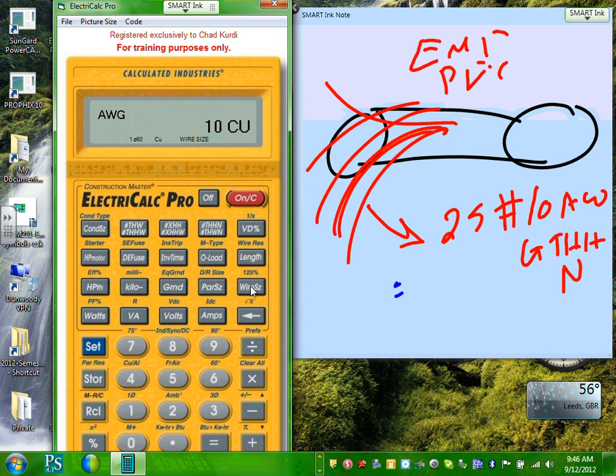Okay, so here's number 10, copper. It defaults to copper, by the way. Now number 10, that's the first thing. How many conductors do I have? 25. So type 25. Do you guys see the insulations here? Do you see THHN? First type 25 and then hit THHN. You have just told the calculator, I want you to accommodate for 25 THHN conductors. Each one of them is number 10. Cool? Everybody's okay? Now hit the conduit.